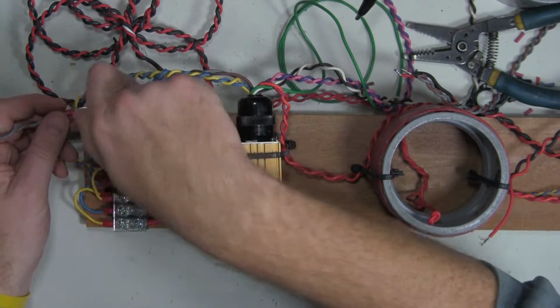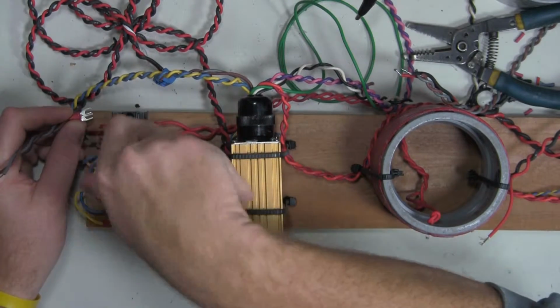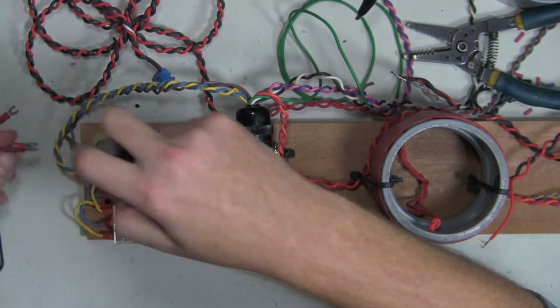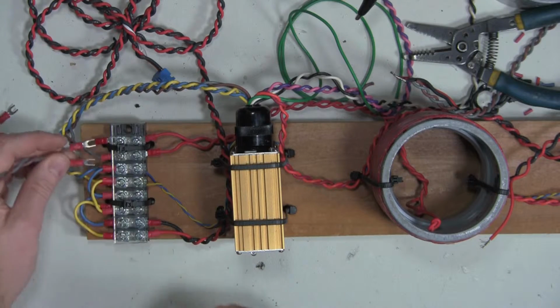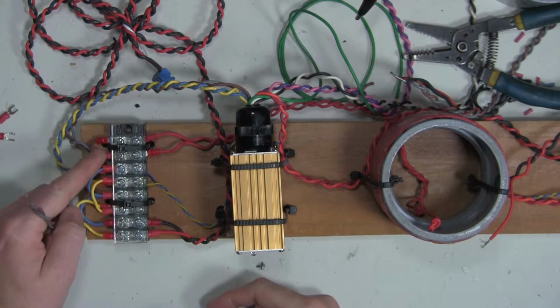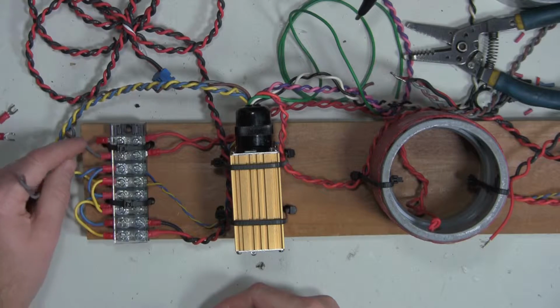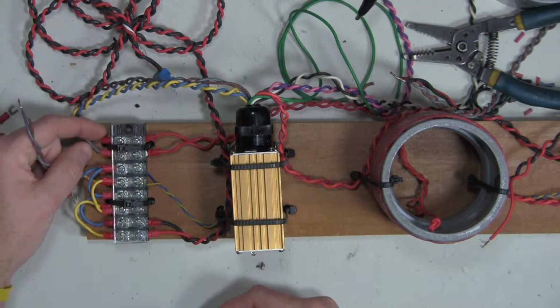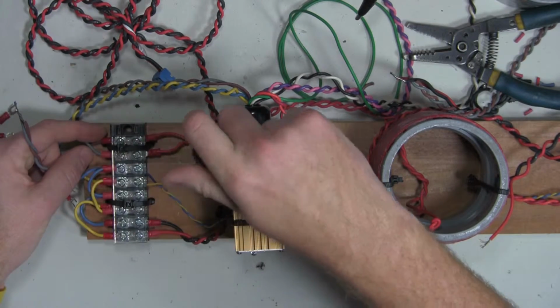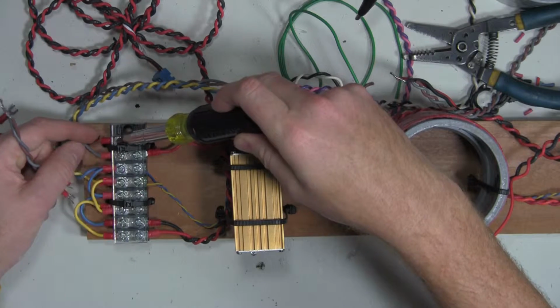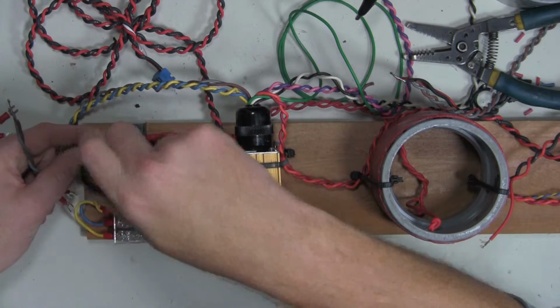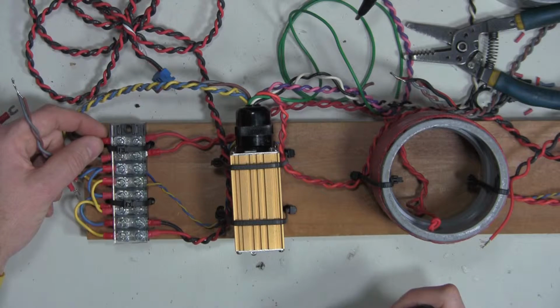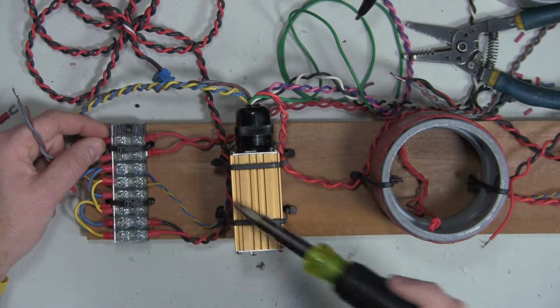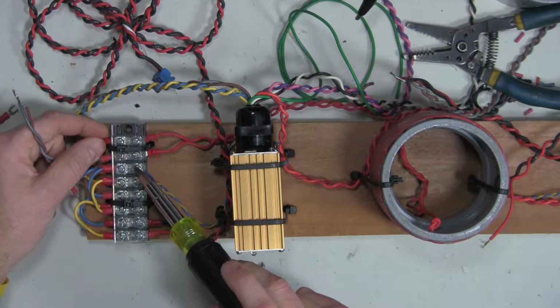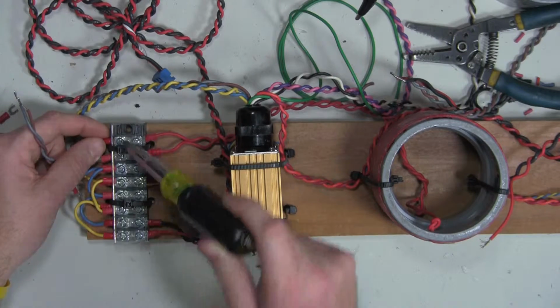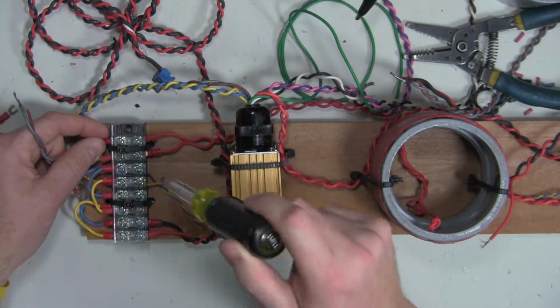That way, if you are unscrewing and screwing these terminal connectors in and out, you don't have to worry about those coming out. Like you can see exactly what happened here. You could just see how this one's coming out. If you put ring terminals on there, unscrew the screw all the way out, put a ring terminal in there and then screw it on there. You don't have to worry about it coming out unless you back the screw all the way out. And this ring kind of prevents you from doing that. Well, actually, this ring in combination with the washer that holds these down.